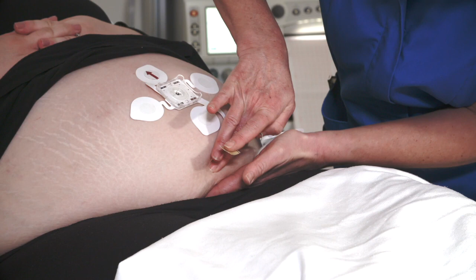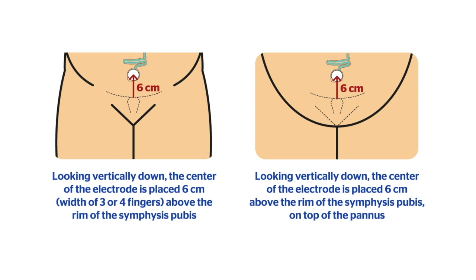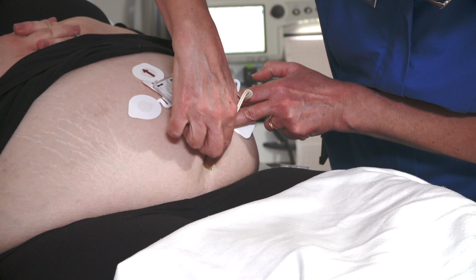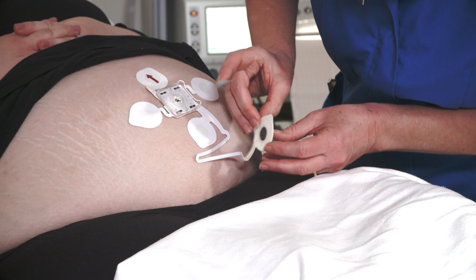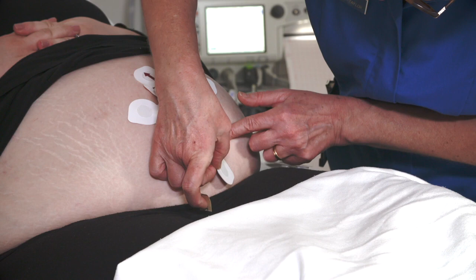When the mom has a pannus, you will need to estimate on the upper surface of the pannus, where the rim of the symphysis pubis would be if you could see vertically down. Place the electrode center 6 cm above this location. Once you have confirmed the placement point, remove the electrode backing so you are ready to stick the electrode down. Exfoliate the skin so that the center of the exfoliation cross aligns with this point. Do not lose sight of this point, and center the electrode over it, sticking it down firmly, trying to avoid pressing the central gel area of the electrode.